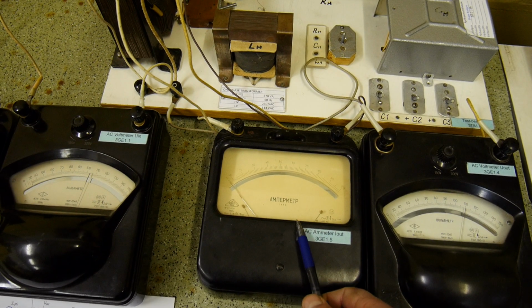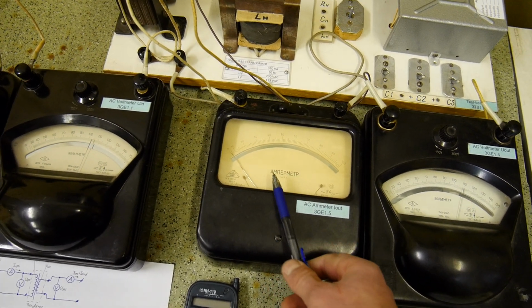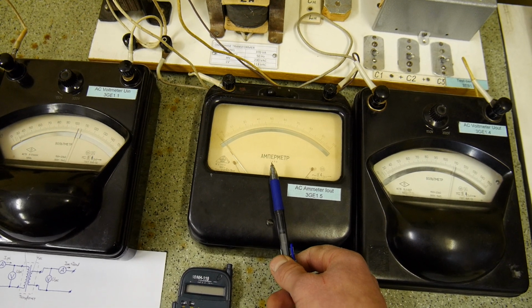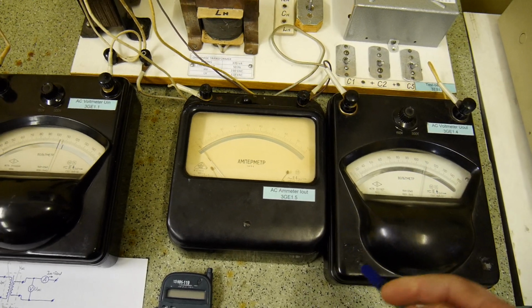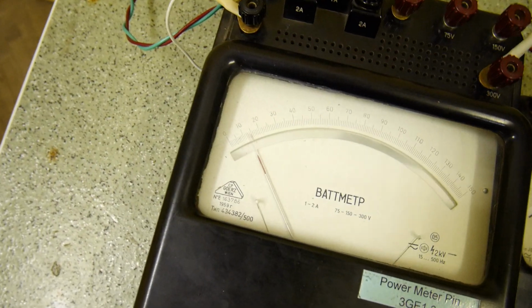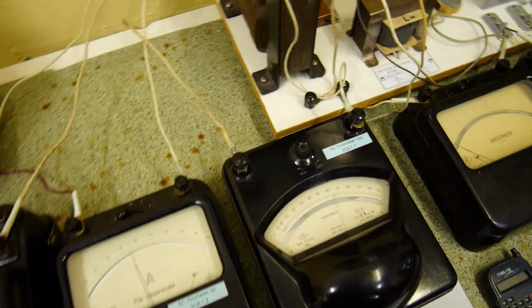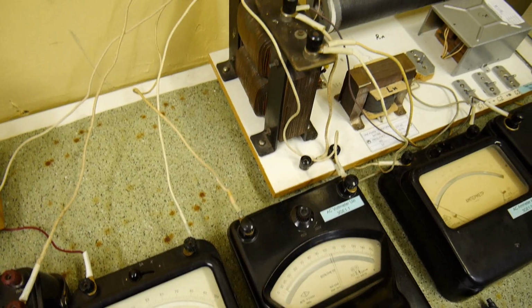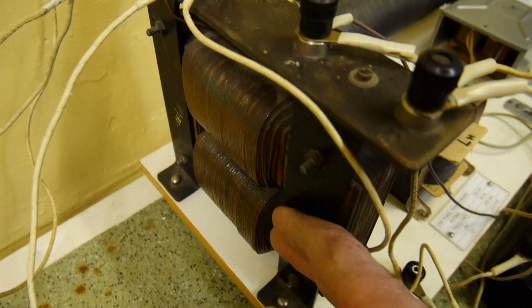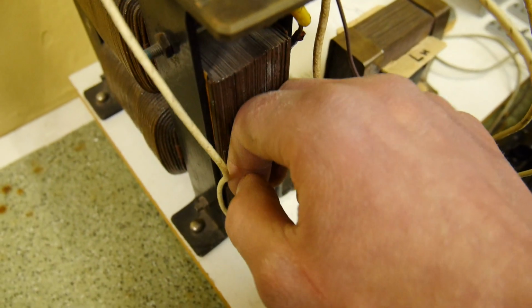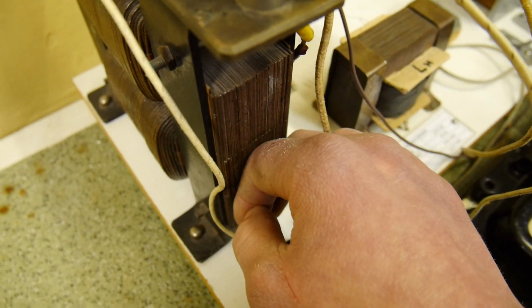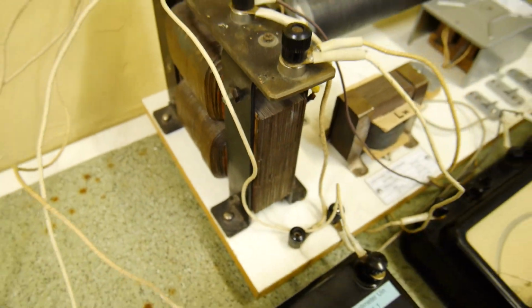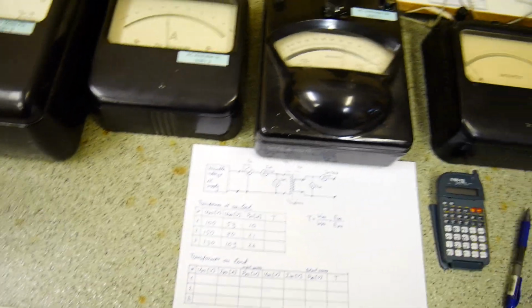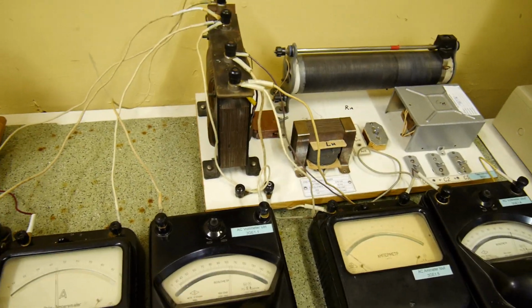So, where is the joke? At first, we do not have any connected load, so we do not have any consumed current, so 0 times voltage gives us 0, so we consume nothing. However, the transformer consumes some power. It means that it consumes, but it produces nothing. Where is the joke? It's not a joke. Actually, these are losses. This is the eddy current loss, and these losses cause an increase in the temperature of the core. So it slightly increases its temperature. So these 26 watts are used to increase the temperature of the core, and these are simply lost.